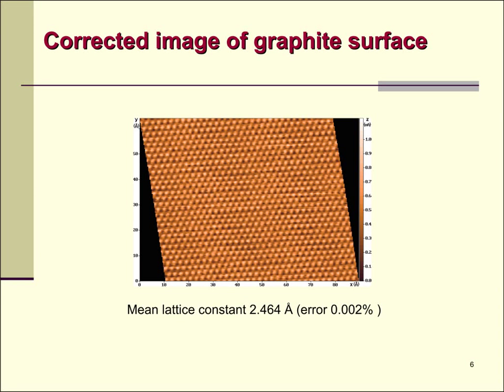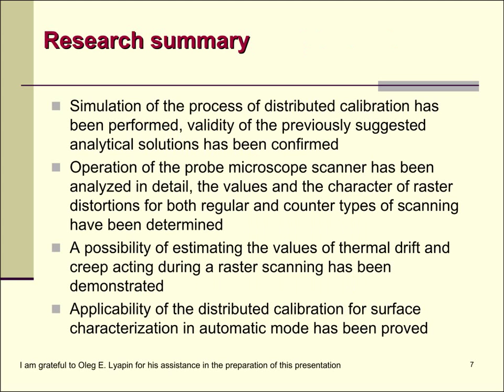On this slide, a corrected image of the graphite surface is shown. The mean lattice constant in the image corresponds to the nominal value of 2.464 angstroms. The residual relative error of the measurement makes 0.002 percent. Non-linear correction of the image has been performed by the obtained regression surfaces using the formula derived in the first paper of the series.